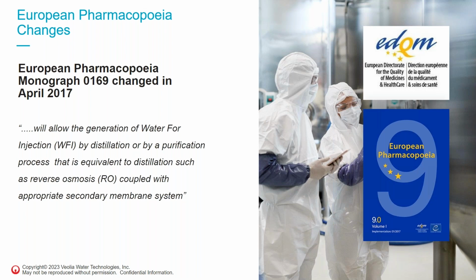And one of the things that changed, and that's allowing us to use membrane systems, is that, as you may remember, the USP had relaxed its method for producing WFI water so that we could use membrane-based systems, and it relaxed that many years ago. The Japanese pharmacopoeia had done that as well, but the European pharmacopoeia still required manufacturers to use the distillation method. So generally, everybody around the world, if they wanted to sell a drug globally, including into Europe, the default was always to go down the distillation unit because it covered every market.